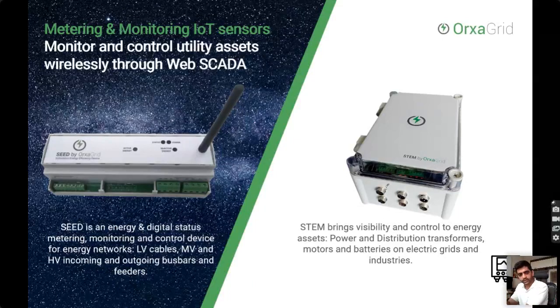on monitoring individual feeders. So the idea is that instead of doing a hardwired cable laying with trenches and all of that, you install simple SEED units on each control panel of the feeder, and the device has inbuilt wireless communications, either Bluetooth or Wi-Fi, to interact with the secure gateway. The device also comes with inbuilt Modbus for hardwired communication to legacy systems, either through RTUs and so on. So SEED is an energy and digital status metering, monitoring, and control device for energy networks, low voltage cables, medium voltage cables, and incoming outgoing bus bars, and so on.